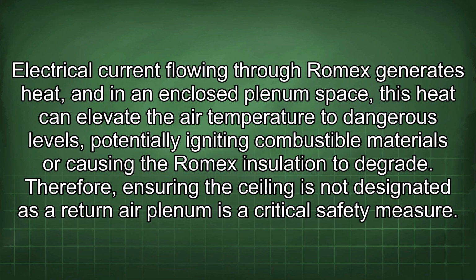Electrical current flowing through Romex generates heat, and in an enclosed plenum space, this heat can elevate the air temperature to dangerous levels, potentially igniting combustible materials or causing the Romex insulation to degrade. Therefore, ensuring the ceiling is not designated as a return air plenum is a critical safety measure.